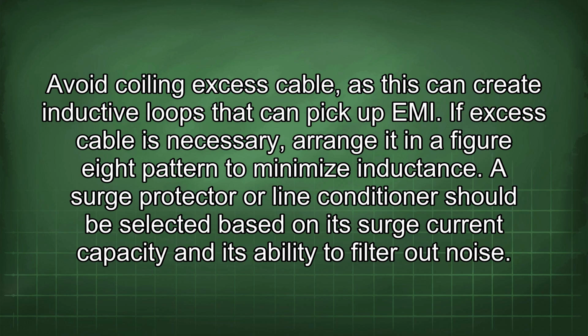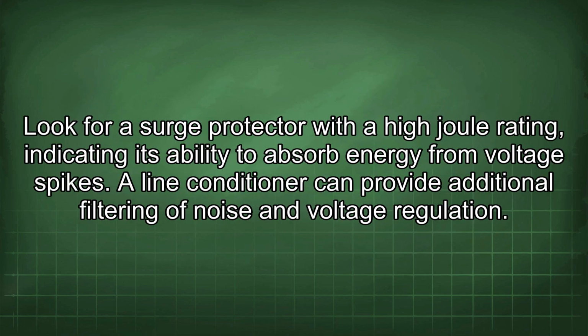A surge protector or line conditioner should be selected based on its surge current capacity and its ability to filter out noise. Look for a surge protector with a high joule rating, indicating its ability to absorb energy from voltage spikes. A line conditioner can provide additional filtering of noise and voltage regulation.